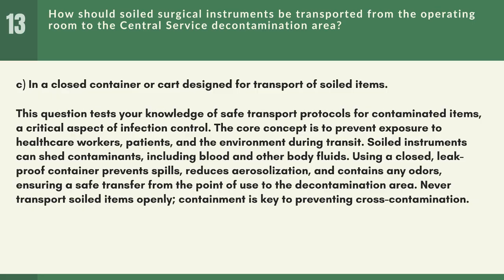Soiled instruments can shed contaminants, including blood and other body fluids. Using a closed, leak-proof container prevents spills, reduces aerosolization, and contains any odors, ensuring a safe transfer from the point of use to the decontamination area. Never transport soiled items openly. Containment is key to preventing cross-contamination.